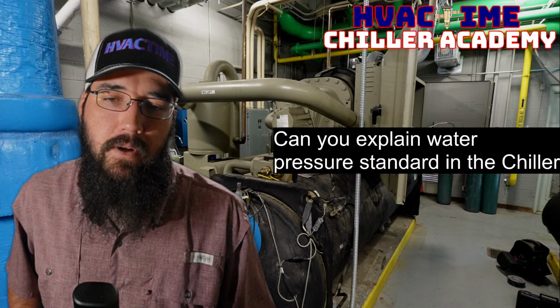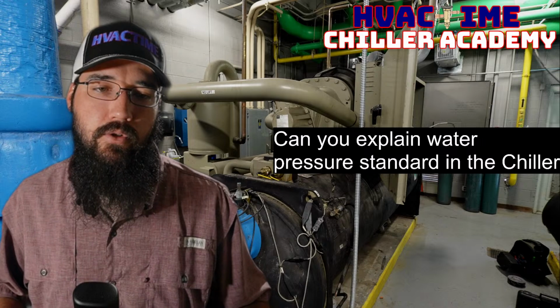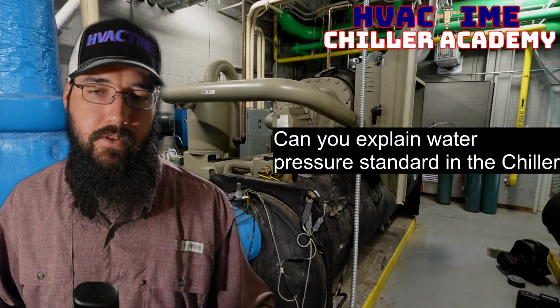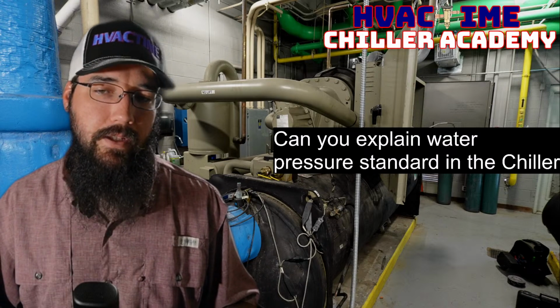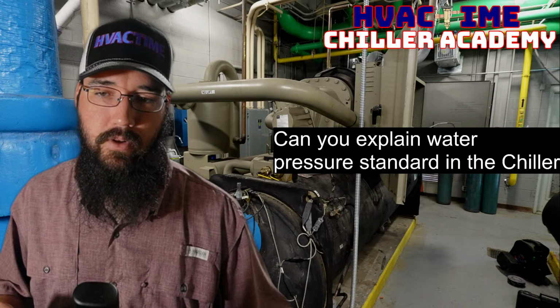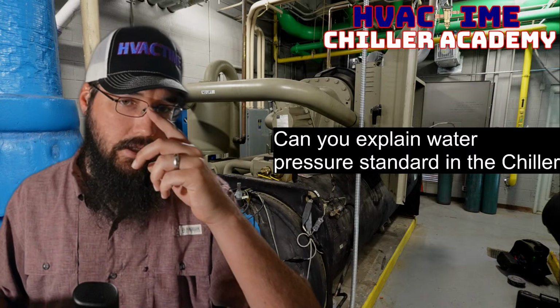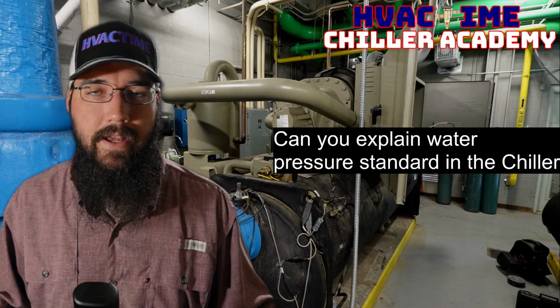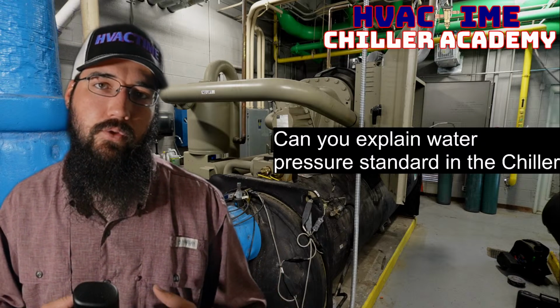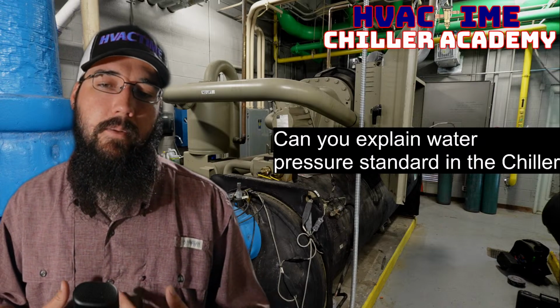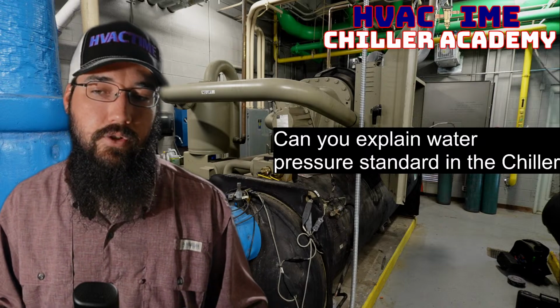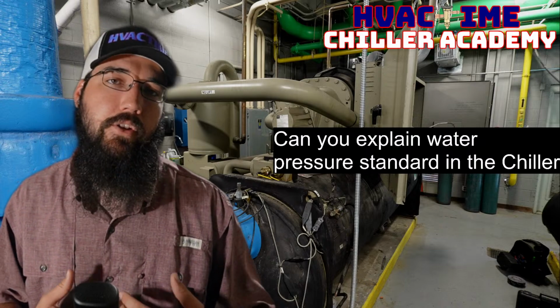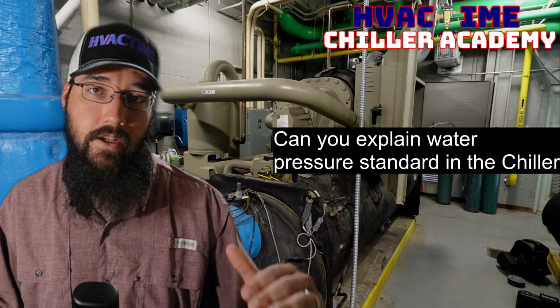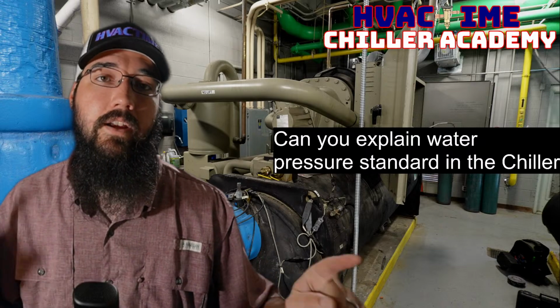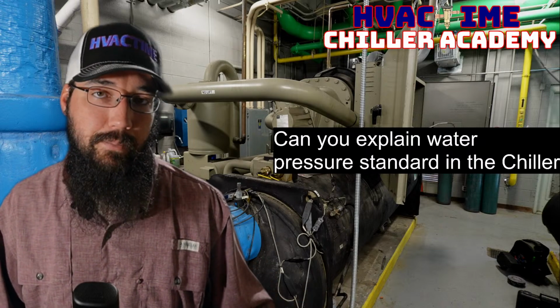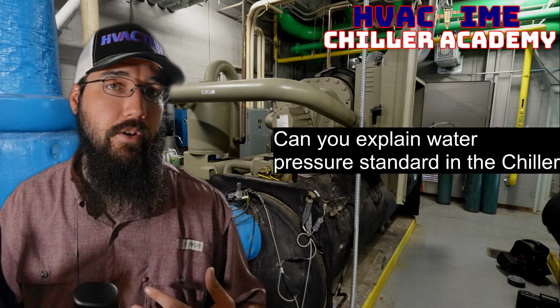So by water pressure standard, we could go two ways with this, right? We could either go with your DP, or we could go with your actual physical pressure, say the loop pressure. I'm going to start with DP here, and I actually have a service procedure I wrote on this to help walk you through the process of determining what your DP should be. Because ultimately, if we're trying to measure flow, then we use DP, differential pressure, so your inlet and leaving pressure on the water side. The difference between them is your flow DP, or your heat exchanger DP, and this is true for evaporator or condenser.